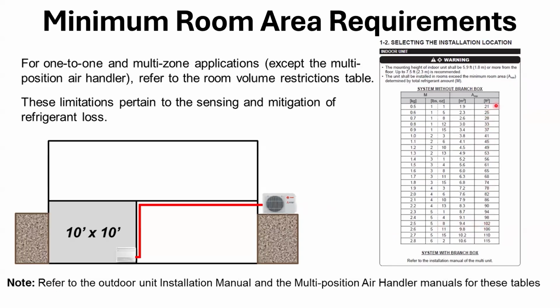As you go down and the room gets smaller, say to a 33 square foot room, which is really small, like a closet, that system can only have 1 pound, 12 ounces in it. Meaning you can't put that unit in a 33 square foot room. And it makes sense: the smaller the room, the more the concern about mitigating the refrigerant leaking in that room. So that's what they're looking at, the amount of refrigerant based on the square size of that room.